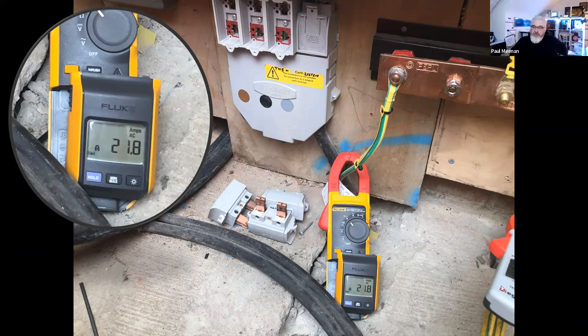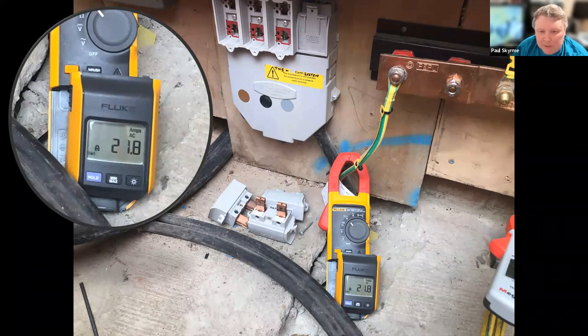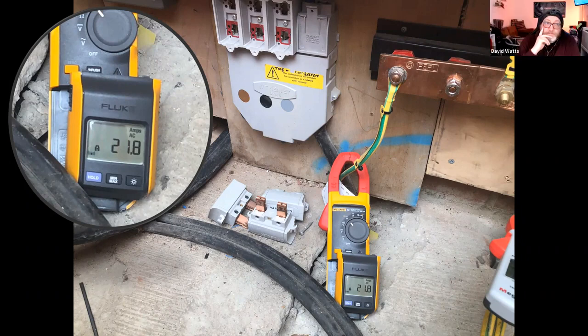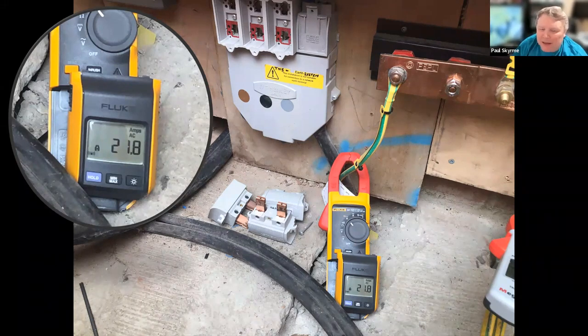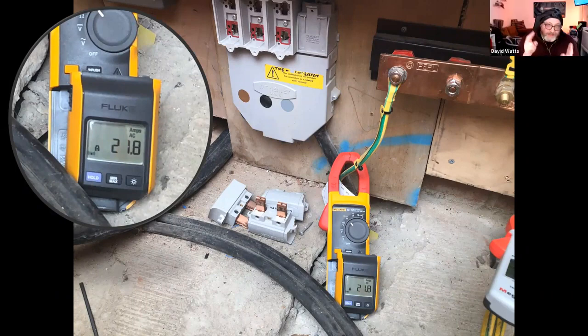Paul's thoughts: the thing is, we're not going to know. Protection-wise, obviously upstream fusing, like Dave said, 100 amps whatever, but then you've got this relying on the upstream fusing to disconnect when you haven't actually got a fault - it's no fault, we've not got a fault condition, which is never going to happen. You know, we've got 21.8 amps there. So if we looked at the Joule heating, as it were, I squared T, there's a lot of heating that could go on with that. And you will never know the voltage behind it until you undo that M8 nut or whatever it is and pop that wire off - you've actually got to disconnect it and then test across it.